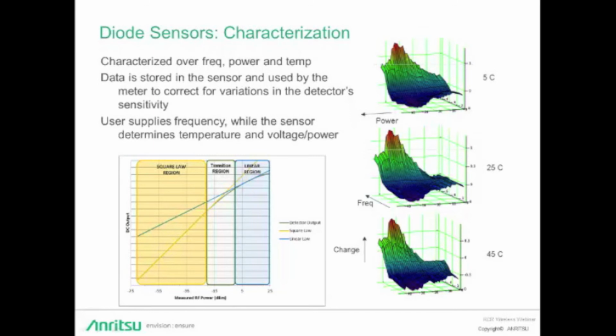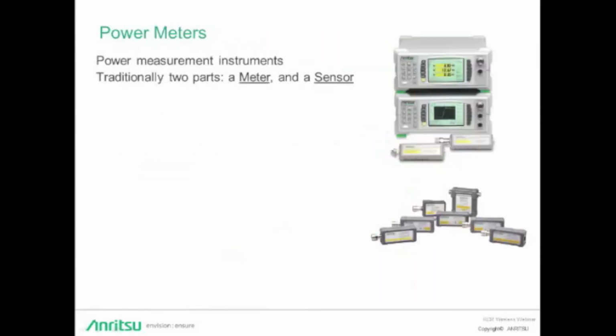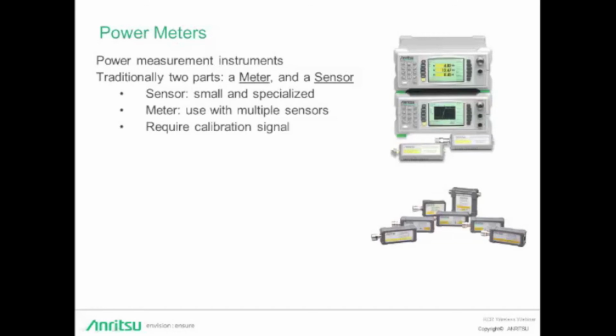So we mentioned that a meter uses characterization data to correct for variations in the detector sensitivity. Let's talk about the role of a meter and what's currently available. Traditionally, power measurement instruments have been broken into two parts, the meter and the sensor. By keeping the sensors separate, they can be small. This enables the sensor to be placed close to the DUT, minimizing RF cabling. Sensors can also be specialized. For example, they can be thermal or diode. They can focus on CW, RMS, or peak measurements. Keeping them separate from the meter also allows reusing multiple sensors with the same meter. However, a trade-off of keeping the sensors separate is that the user will have to perform a calibration to compensate for each different combination. We'll talk more about the traditional meters in the next slide.